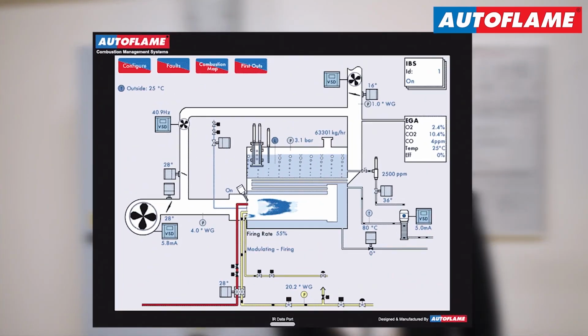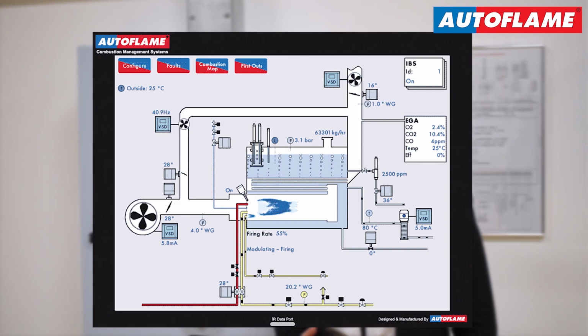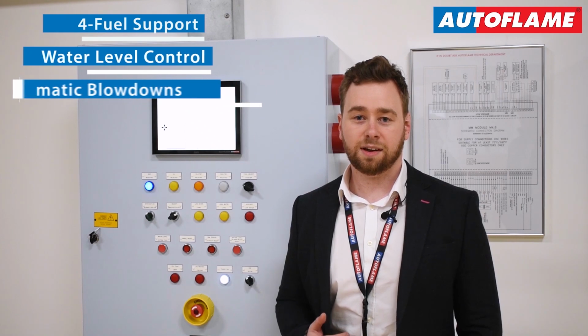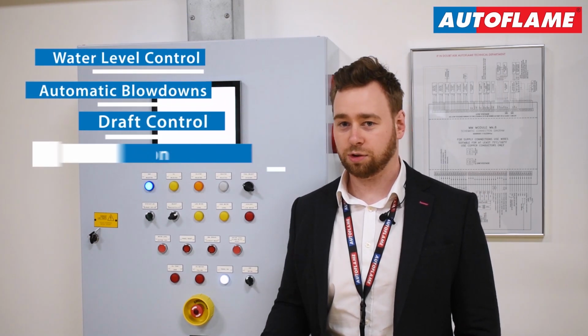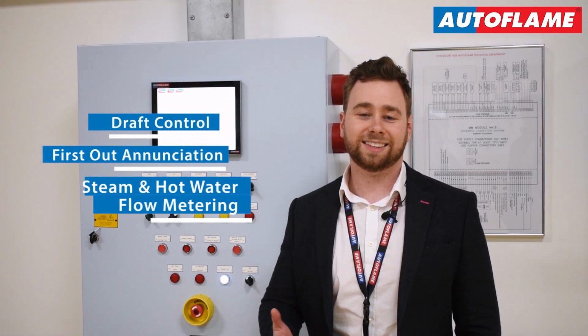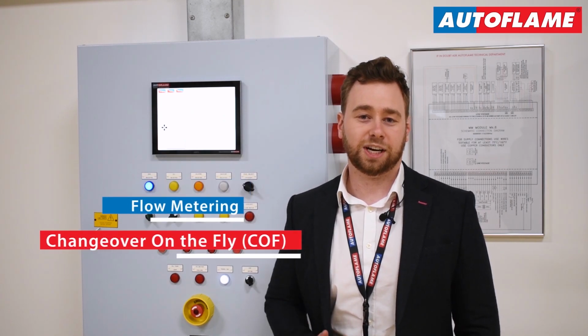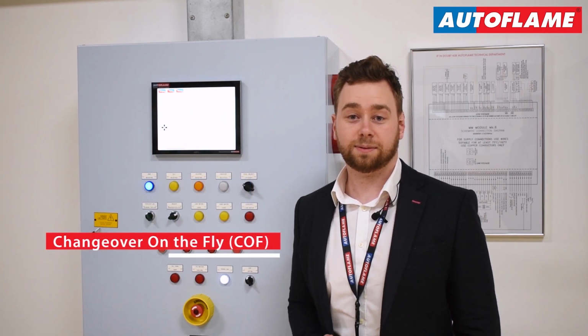The Mark 8 MM is a more integrated boiler controller, managing every aspect of the burner, same as the Mini Mark 8, but also incorporating 4 fuel support, water level control, automatic blowdowns, first out annunciation, draft control, steam flow metering, and our latest expansion feature, fuel changeover on the fly, or COF.